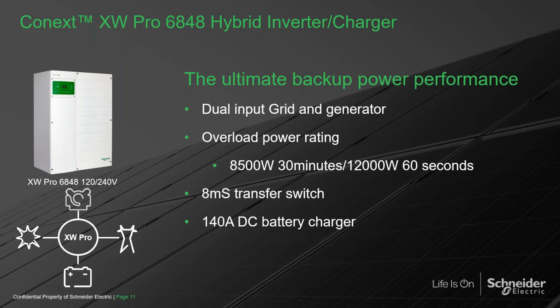So ultimate backup and performance. The XW Pro has a dual input for grid and generator. So again, that allows us to be compatible with almost any generator. We can synchronize when the generator is running, it powers the loads and charges the batteries at the same time. And generator power is typically outside of what your grid power would be. So that allows us to widen those input windows so we can work with those generators. The overload power rating, as I mentioned, is 8,500 watts for 30 minutes, 12 kilowatts for 60 seconds.